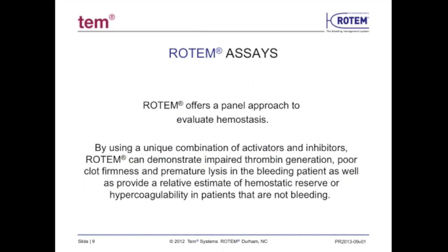Because bleeding in the clinical setting is often multifactorial, Rotem offers a panel approach to evaluate hemostasis imbalance and to guide transfusion therapy. By using a unique combination of activators and inhibitors, Rotem can demonstrate impaired thrombin generation, poor clot firmness, and premature lysis in the bleeding patient, as well as provide a relative estimate of hemostatic reserve or hypercoagulability in patients that are not bleeding.